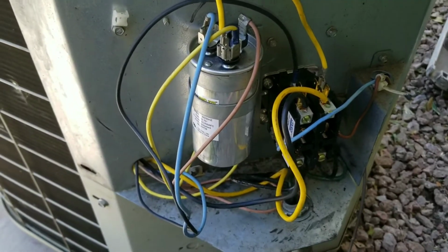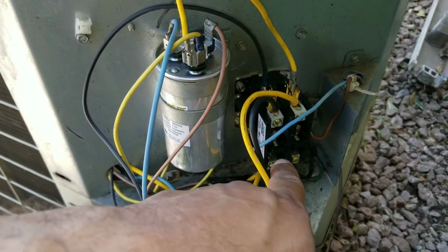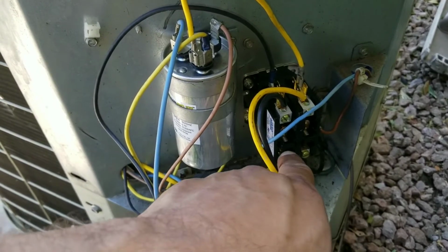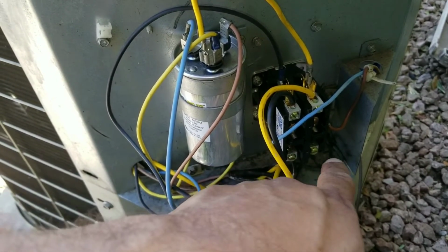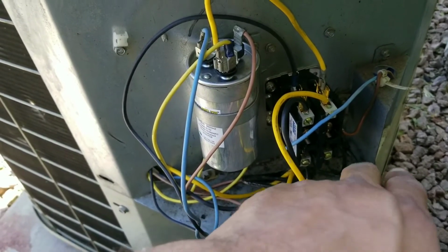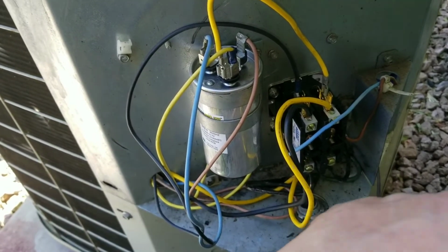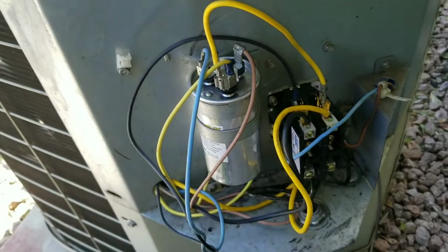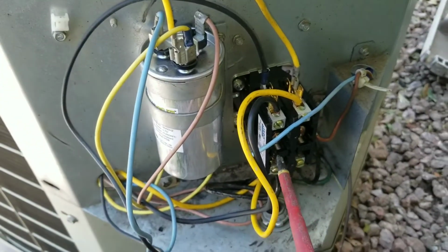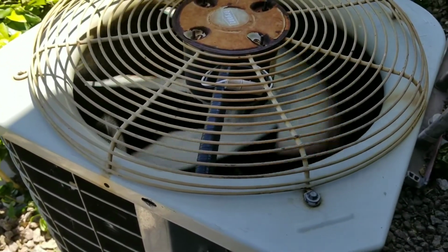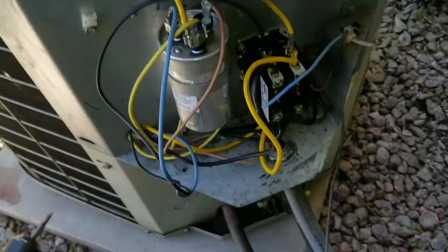Now, if you wanted to test your system, you could simply push the contactor in. We do know the disconnect is plugged in, and we have 240 volts coming in. We should be able to press the contactor and the condensing unit should turn on, because by pressing the contactor and engaging it, you're tricking the system into thinking that the signal came from the thermostat. So go ahead, just be careful not to touch the voltage, obviously. So here, you see the fan motor turn on. You could hear the compressor turn on. And once you remove it and disengage it, the system should turn off.